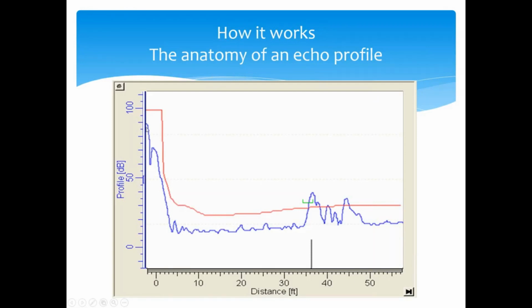So my blue line here is the actual signal return, or the echo profile, that I'm seeing from the ultrasonic or the radar. So what happens is we'll send that signal out from the transducer up here, and it'll come down to some value. That value is what we call the noise floor. Every application is going to have some amount of ambient noise going on in the background. That's what this noise floor is. And then anytime you see a spike here, that's a signal return. So we're now reflecting off of something inside that tank or that vessel. This might be true liquid level, which is what it is in this specific application, but it could also be any sort of obstructions in the vessel.